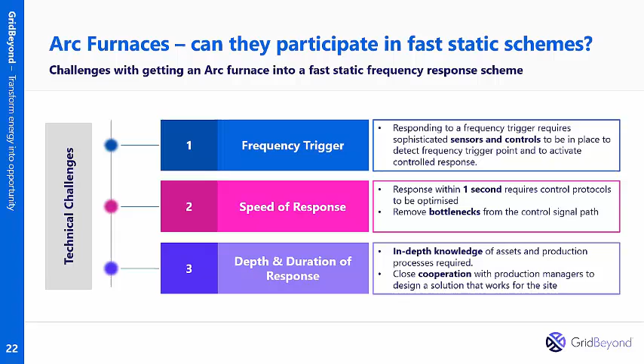Okay, so I suppose this is what we have done. We found on certain sites that our controllers go through a communications panel, then to a site-wide PLC, and then a signal could go to an individual arc furnace PLC, which sends a signal to lift the hydraulics. All that takes time, and that time adds up, and all of a sudden we're not delivering the load shedding within 1 second. So what we try to do is talk directly to the individual arc furnace PLC.